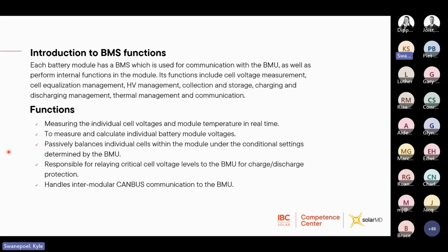Okay, so Alton, just to answer your question quickly, the usable capacity on the battery is the usable capacity. If you go below that, there is cell voltage monitoring to open the relay contact when it reaches the low point. When it reaches that low point, that relay opens, so DC disconnects the battery, and then the battery will wait for 1 hour before it closes the relay again. It will look for charge. If it does not charge above the threshold of where it needs to disconnect, it will disconnect again for another 1 hour.